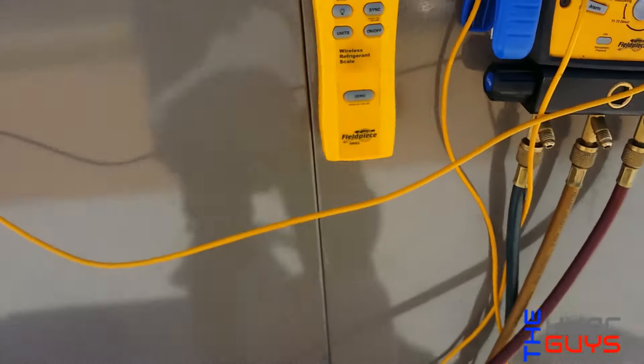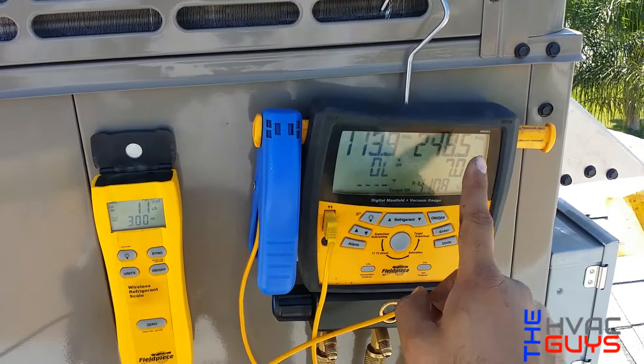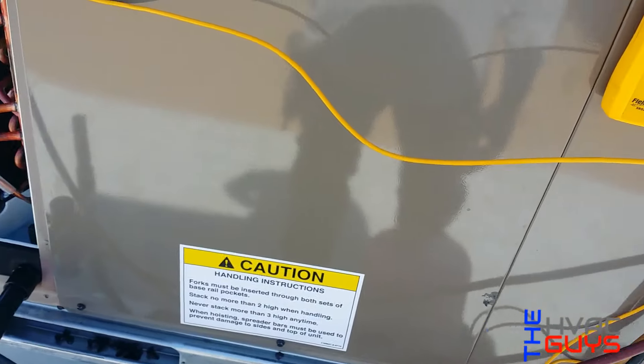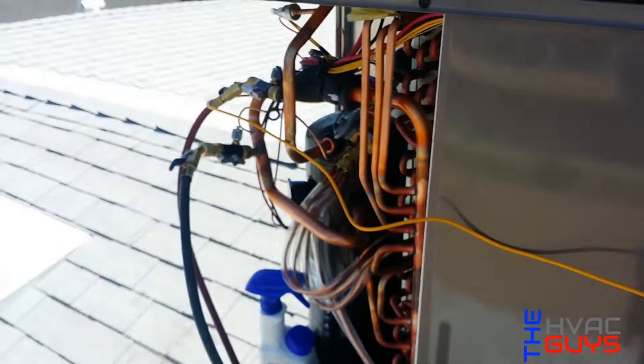So this thing's factory charge — you see right here — factory charge is 14 pounds 4 ounces. We're checking our split. Right now we have 11 pounds and our subcooling is 7, which is good. So it's getting there. I think it's 7 or 8 for our subcooling — we'll target 8.